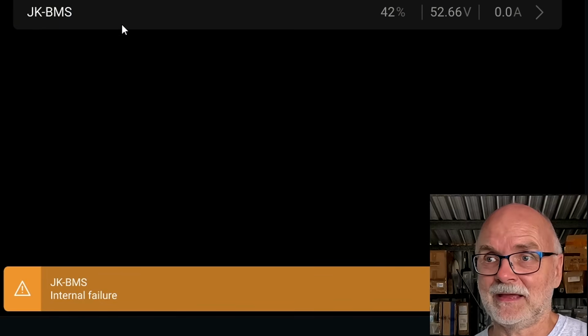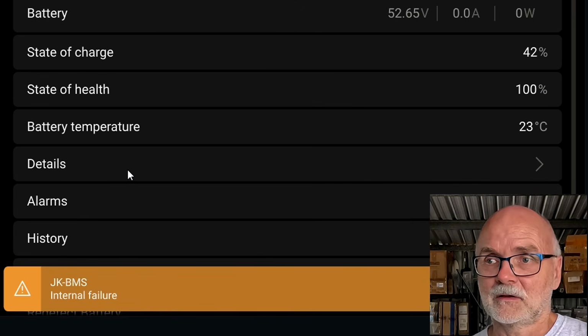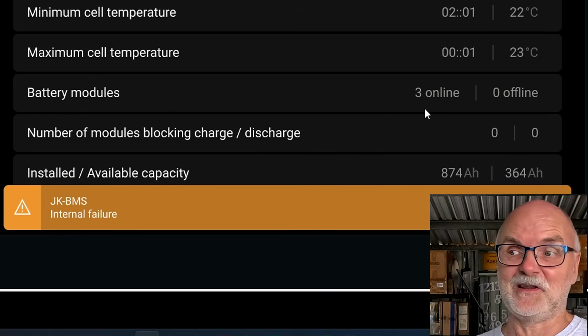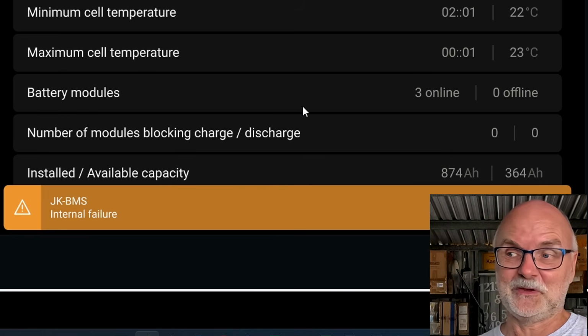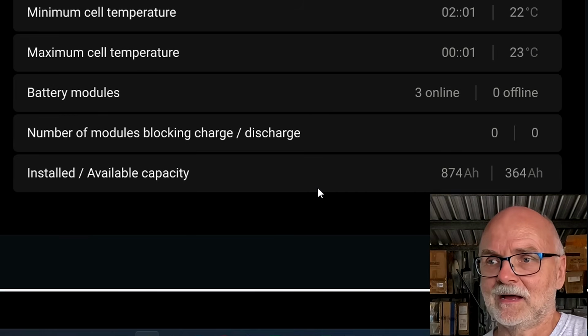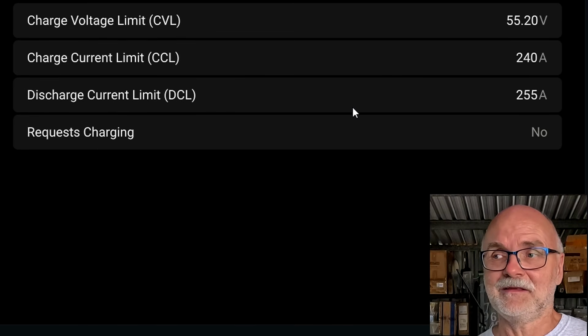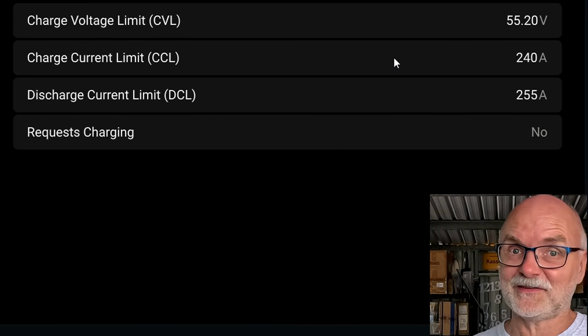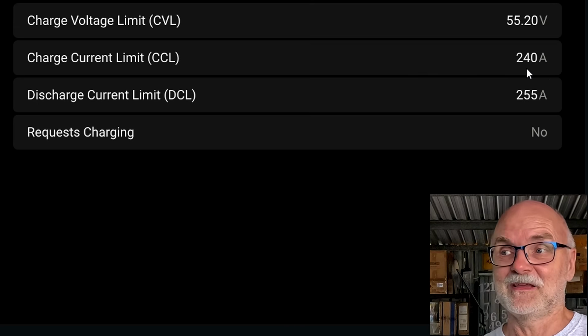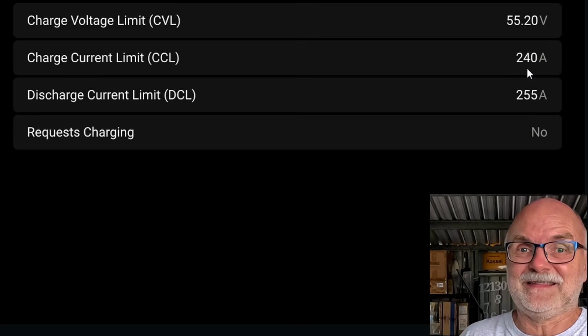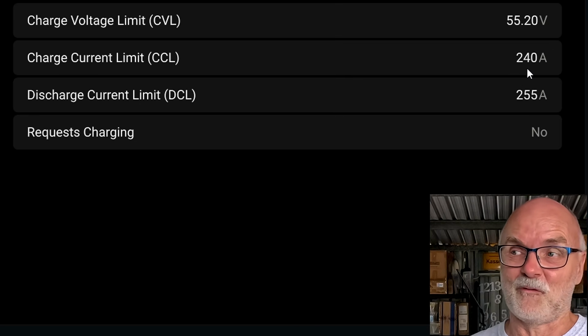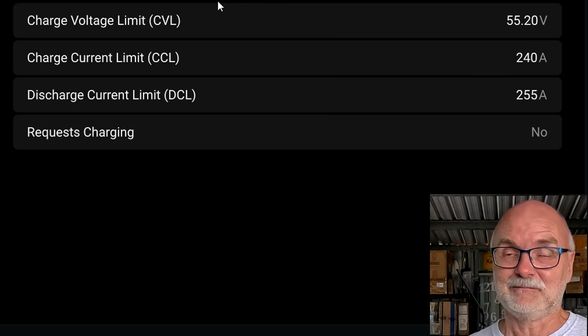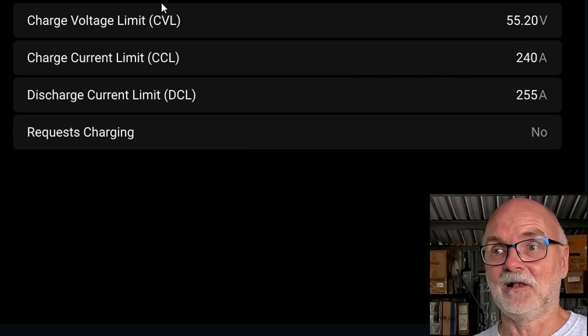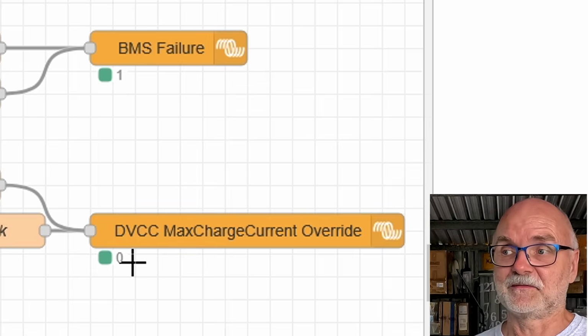So if we go back to the JK-BMS, go in here, go into details. The JK-BMS itself still says we have 3 batteries online, nothing is blocking us, so we keep charging, right? Let me silence this alarm. And here under parameters, the JK-BMS would now request a charge current of 240 amps from your inverter, which is not correct. Something has happened to battery or BMS number 4 and there's no alarm, we still keep charging. But I've overwritten this now with the CCL on 0 amps. There it is, 0 amps.